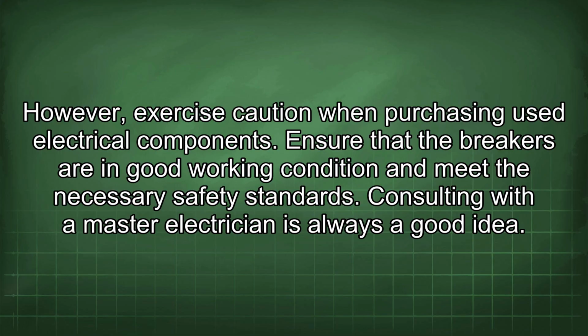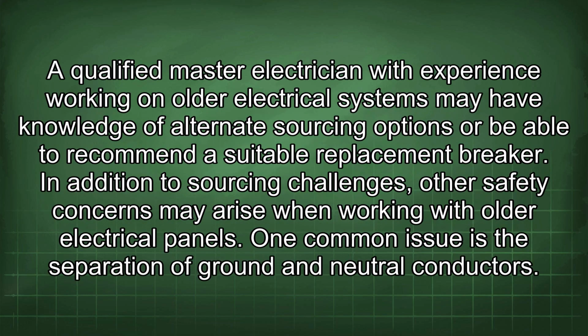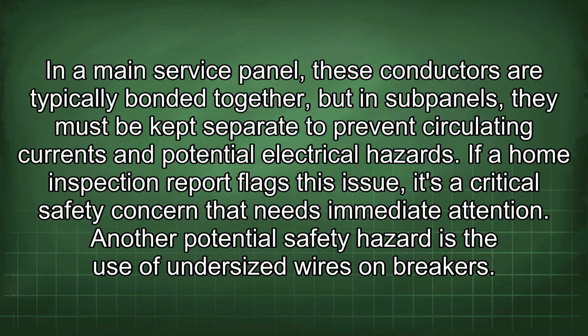Consulting with a master electrician is always a good idea. A qualified master electrician with experience working on older electrical systems may have knowledge of alternate sourcing options or be able to recommend a suitable replacement breaker. In addition to sourcing challenges, other safety concerns may arise when working with older electrical panels. One common issue is the separation of ground and neutral conductors. In a main service panel, these conductors are typically bonded together, but in subpanels, they must be kept separate to prevent circulating currents and potential electrical hazards. If a home inspection report flags this issue, it's a critical safety concern that needs immediate attention.